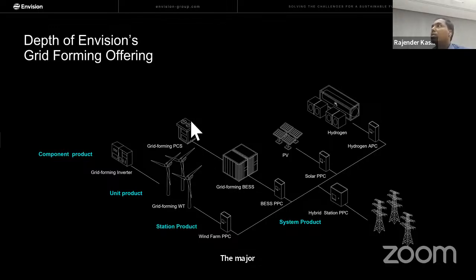The major part, the brain behind this, is the software element of the grid PCS, which interacts between grid forming and grid following. During the grid following time, it is following the frequency levels of the grid. At the same time, when it is switched to grid forming mode, it has to restore the frequency gradients for grid forming operation. So it is a unique requirement, a combination of doing droop and inertia control at the same time. This is what Envision is doing.